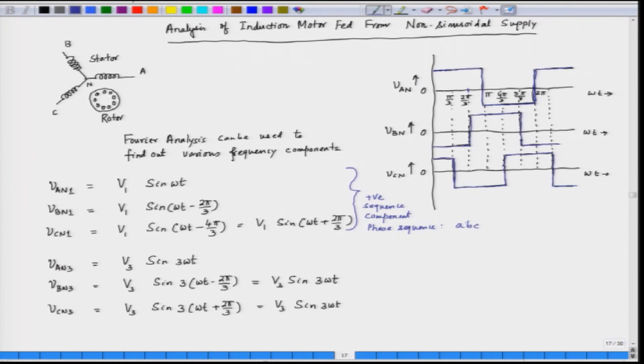A followed by B followed by C, and then it repeats A, B, C. What about the third harmonic? If we see the third harmonic, we see that the third harmonic components are co-phasal — here we have 3ωt, here also we have 3ωt, and the same 3ωt. So they are actually co-phasal, and we can say this is a zero sequence component. It means phase A, phase B, phase C are in the same phase.